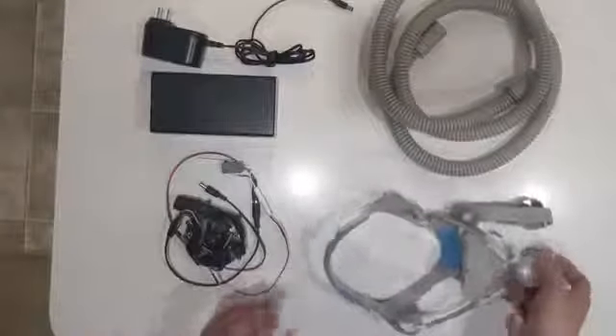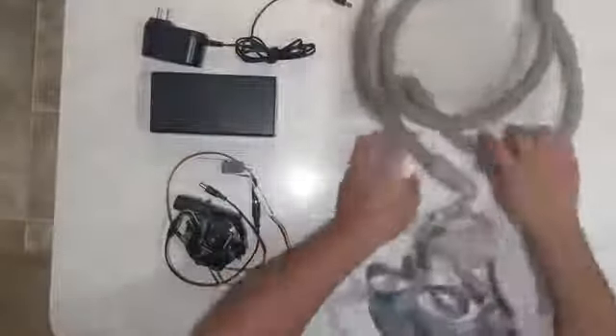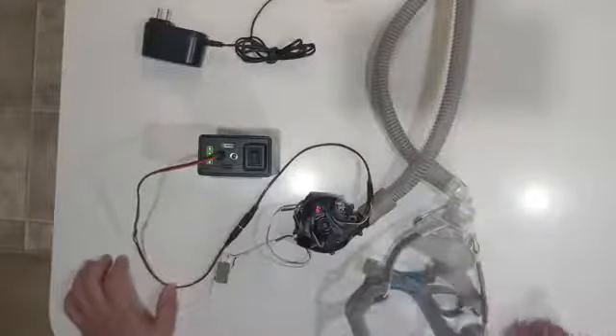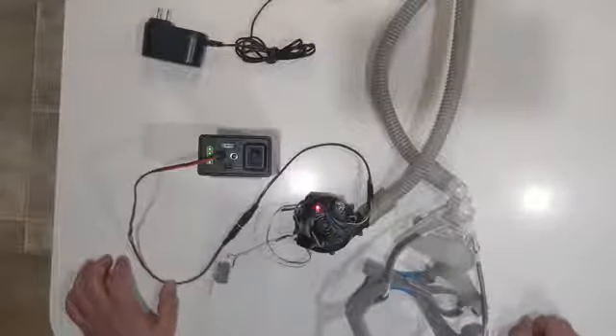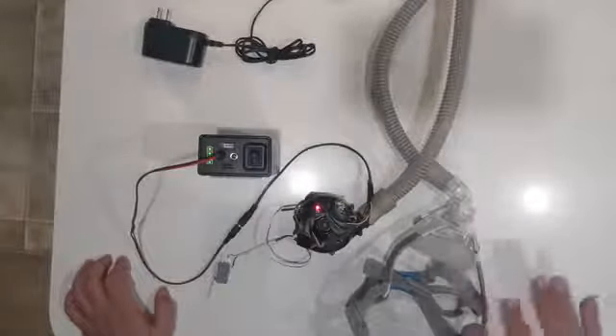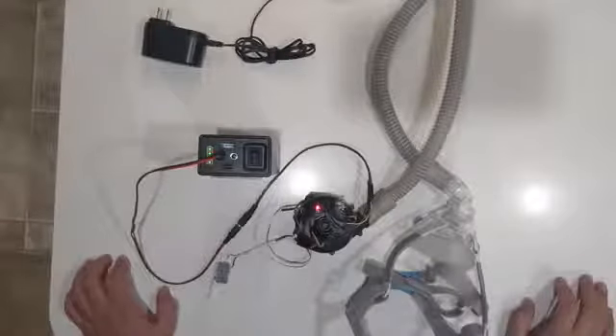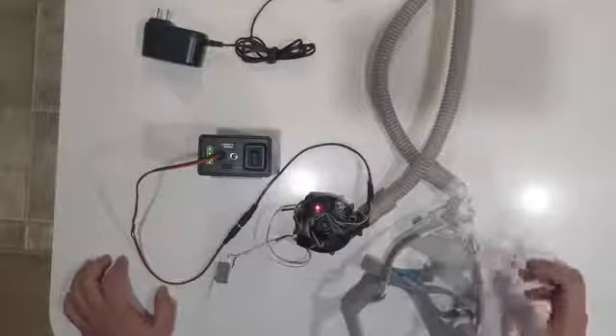Now, putting it together is pretty simple. I just take one end of the breathing tube into the face mask, and the other end of the breathing tube into the blower that has this tapered end, which has been 3D printed on it to make the blower fit. Then I take the DC jack, turn on the battery, and plug it in. You'll hear the motor go through an initialization sequence, and it starts off in a low pressure level CPAP mode. So it's blowing continuously right now with the air pressure, and this will push air into your lungs.